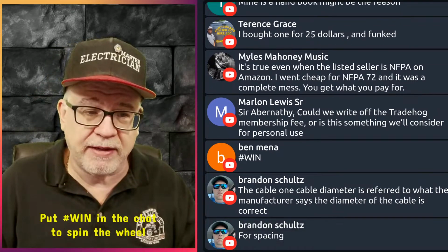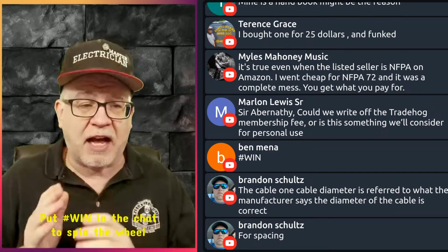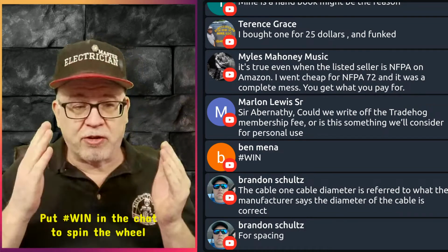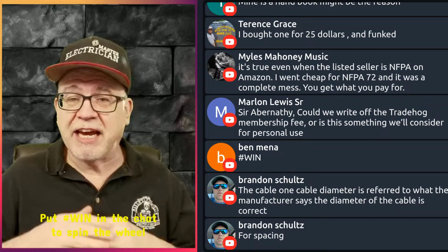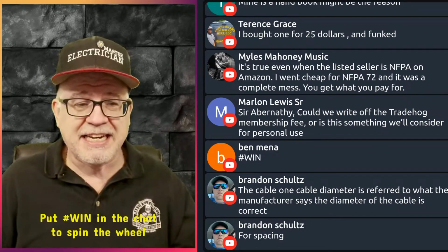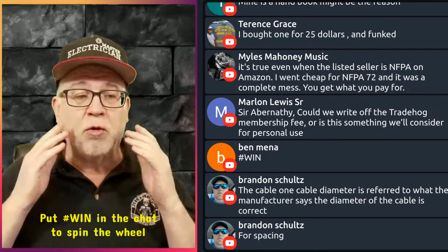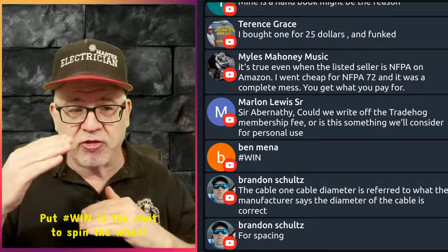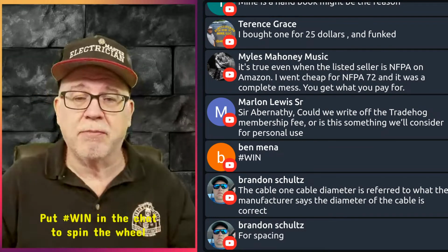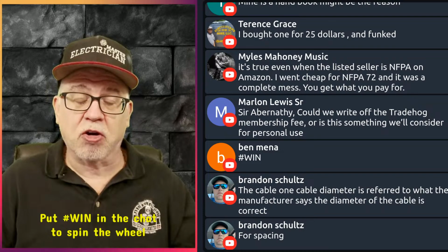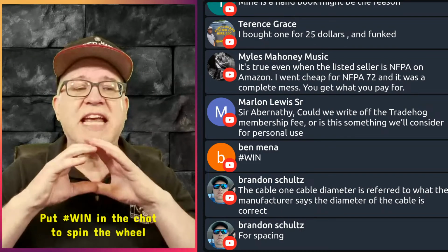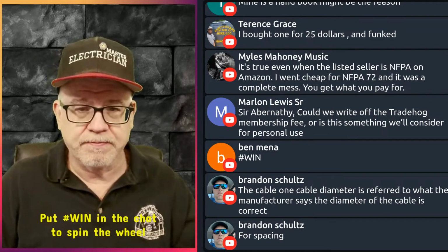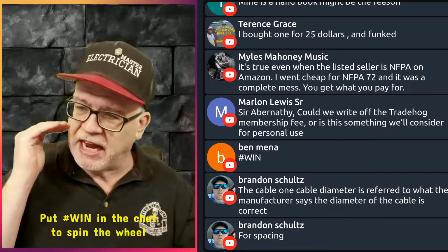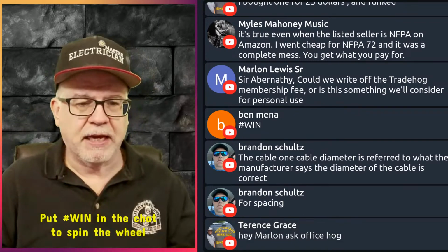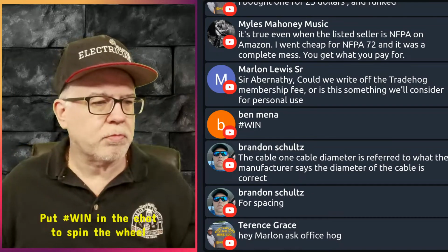And always remember, Brandon, when it says diameter, it's not talking about volume. Diameter is a physical property. Volume is a calculation. Anytime it says diameter, it's the physical property, the diameter across the conductor or across the cable. If it says the area or cross-sectional area, you have to do a calculation. Don't let that confuse you. If it mentions diameter, it's a property, okay? Let's get back to where we're at. Hopefully that clears that up.